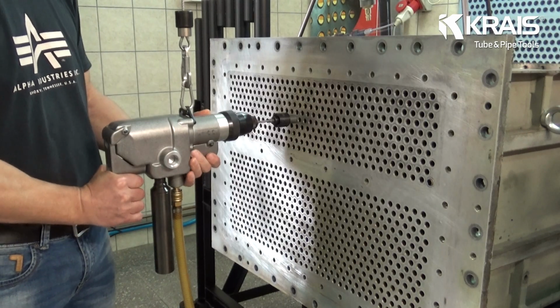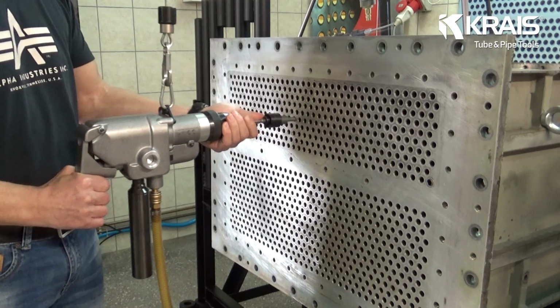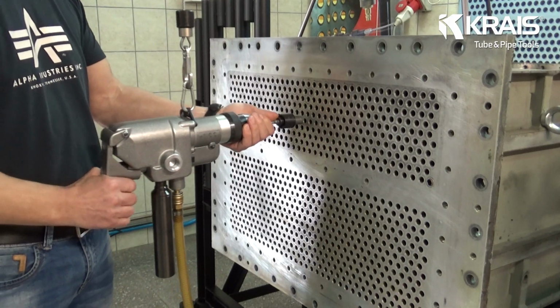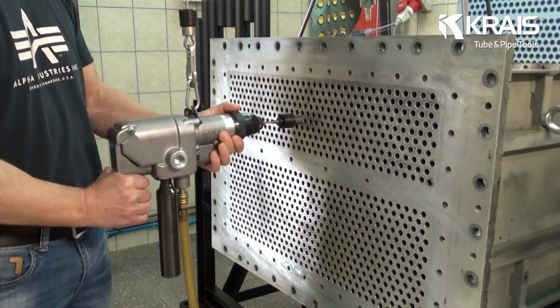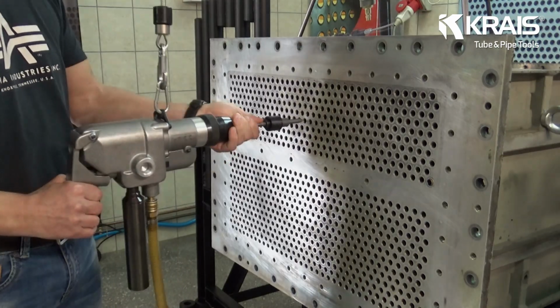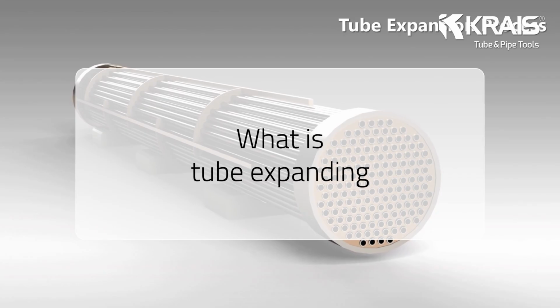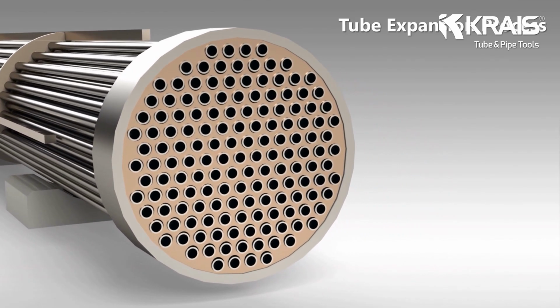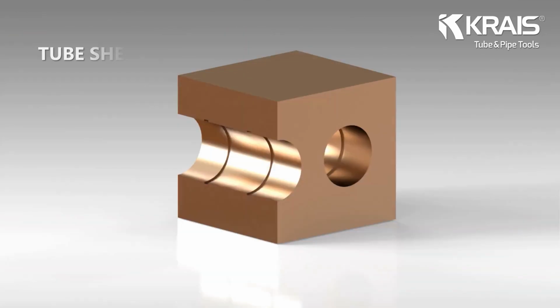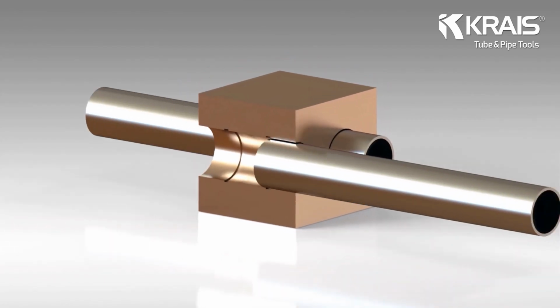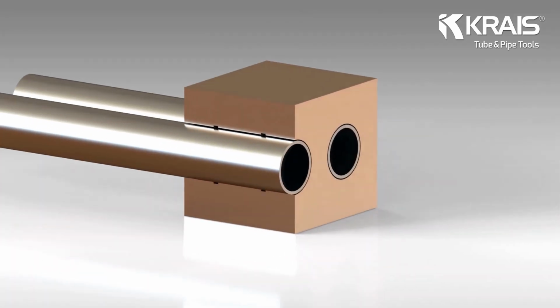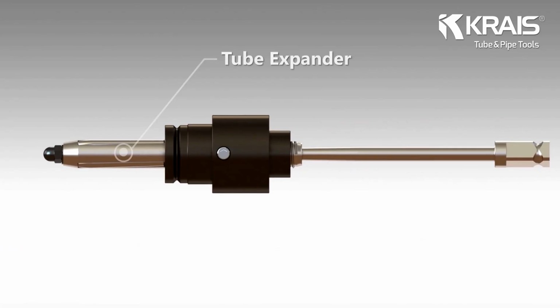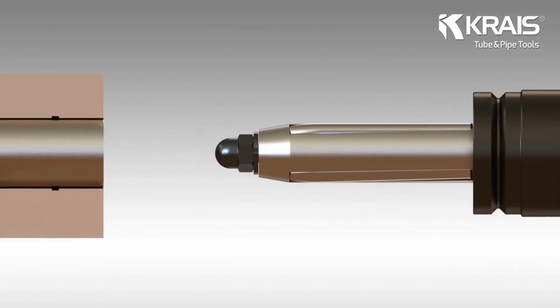Today we will show a practical, decision-oriented way to select a KRAIS tube expander for the job, from small coolers through standard heat exchangers and large condensers to boiler tooling and specialist applications. What is tube expanding? Tube rolling, also referred to as tube expanding, is a controlled plastic deformation of the tube end inside a tube sheet or seat, creating a tight, repeatable tube-to-tube sheet joint.